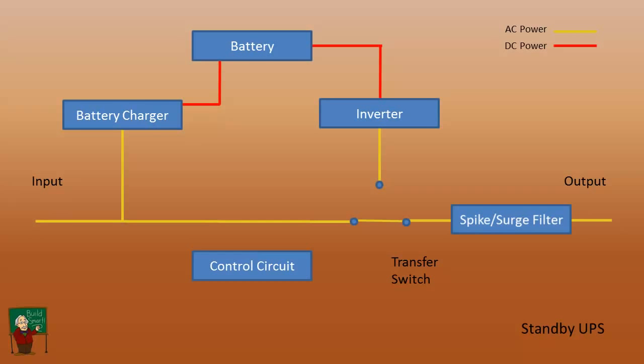Put in a control circuit. This will receive voltage information from the battery. In turn, it will be able to turn on the battery charger when that voltage is too low. It will look at the incoming line voltage, and if that voltage is out of specification, it can activate the inverter and also has a connection to the transfer switch, so it can transfer over to battery power.